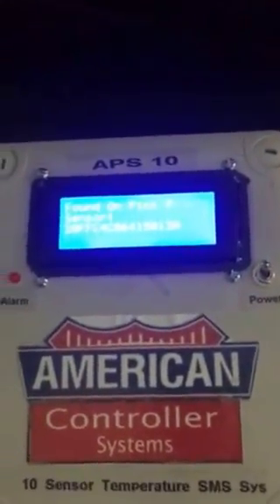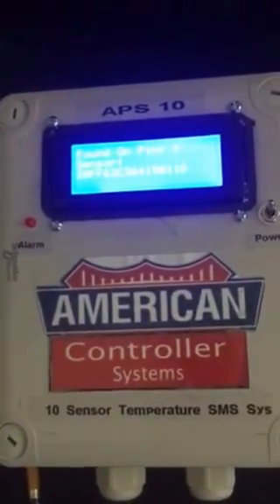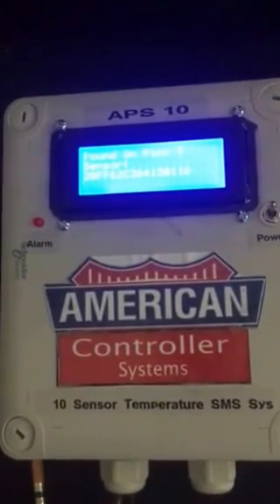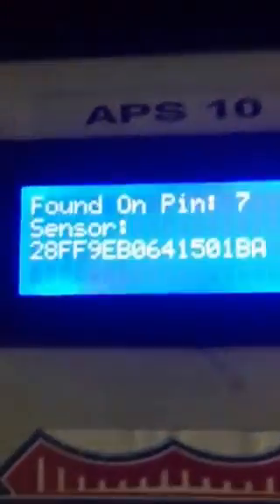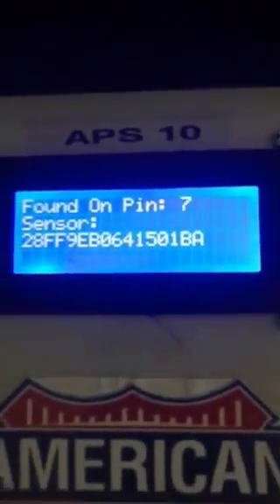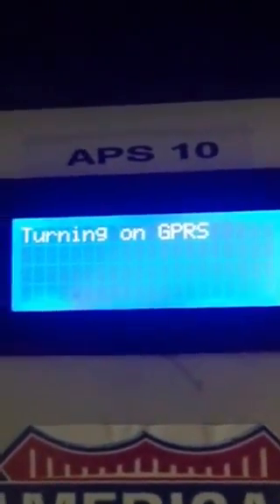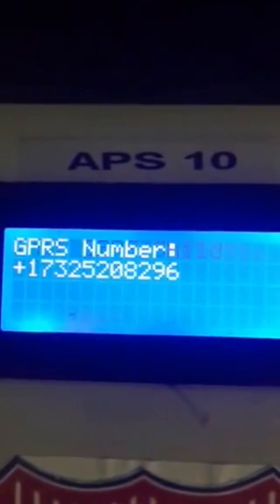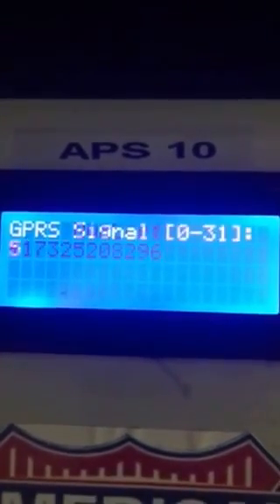After the initial reset, the APS — which stands for Alarm Paging System, model 10, which takes up to 10 sensors — scans for the sensors and gives an ID for each one. It also checks the internal device, like the modem, and tells you whether you have reception. It will tell you the phone number of the SIM card and the signal strength.